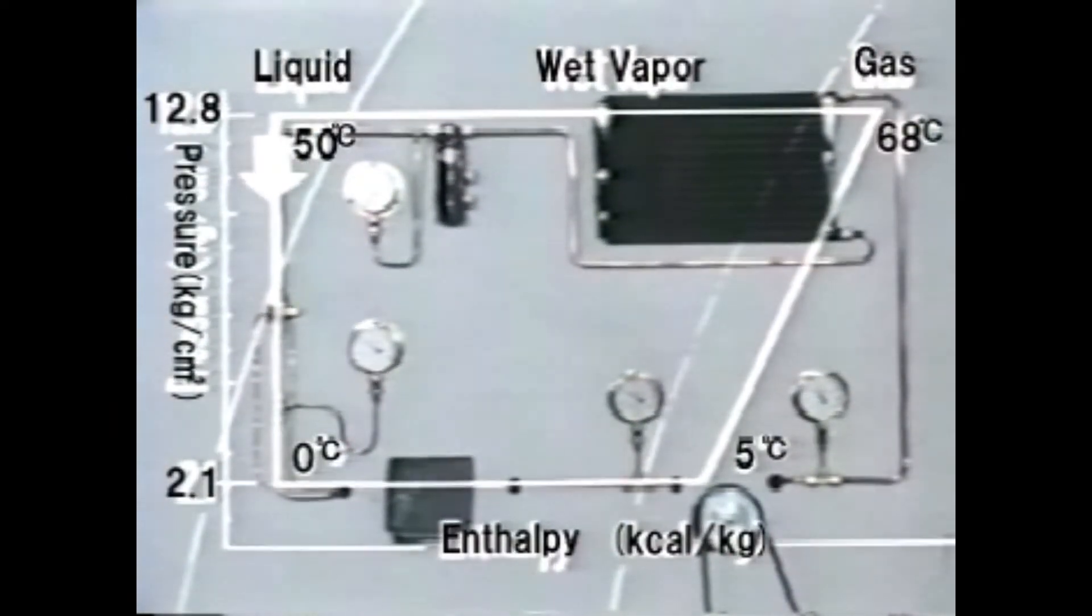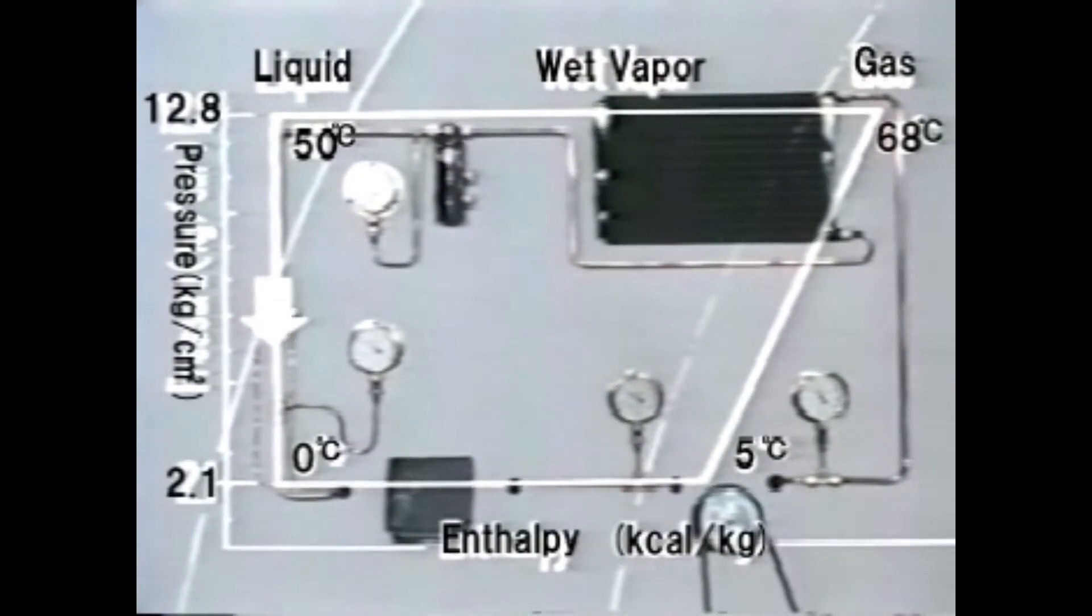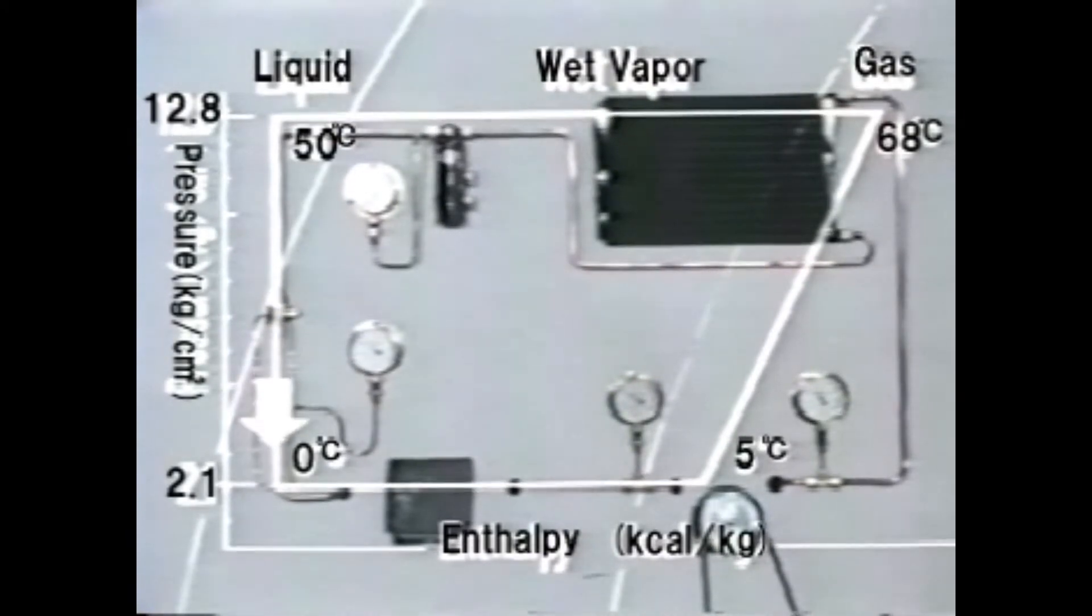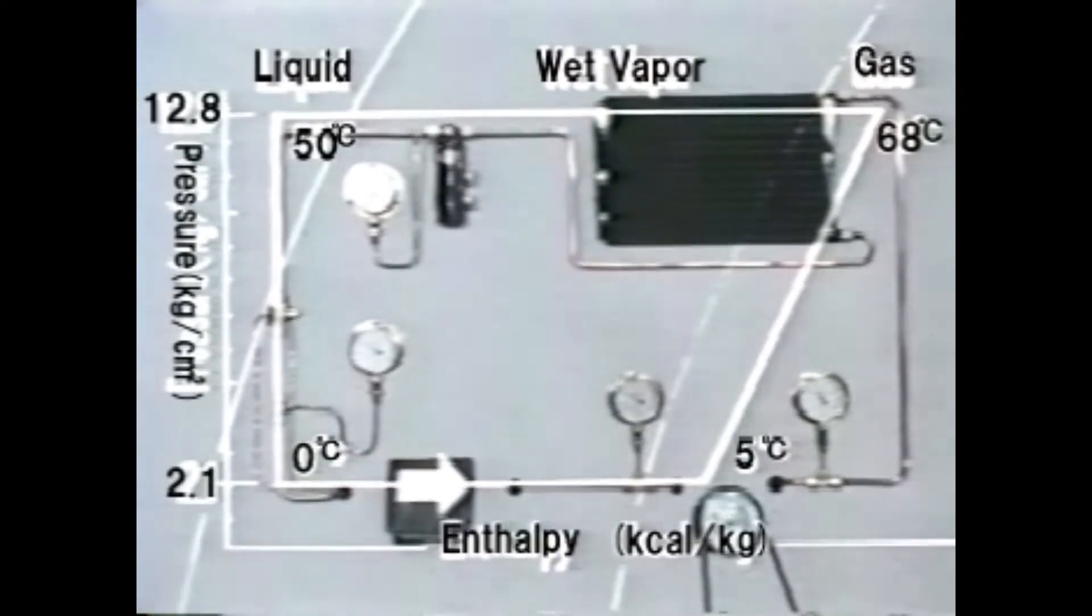In other words, refrigerant at pressure 12.8 kilograms per square centimeter and 50 degrees centigrade is decompressed to pressure 2.1 kilograms per square centimeter by the expansion valve to turn into vapor at zero degrees centigrade.